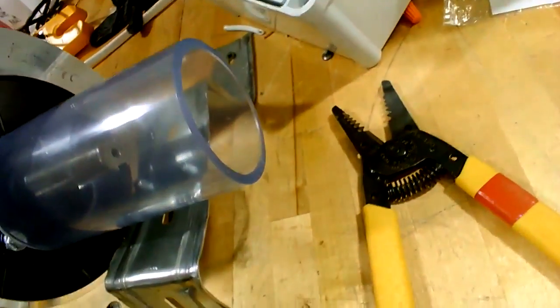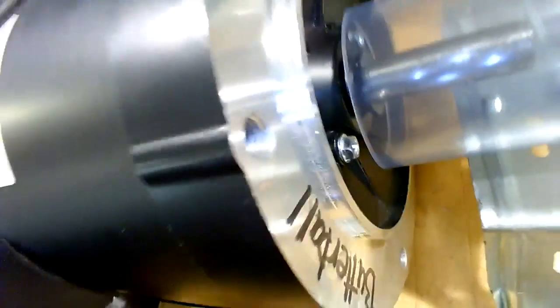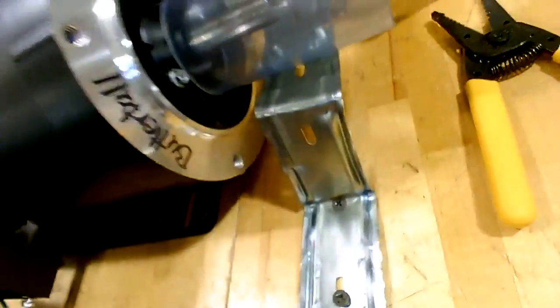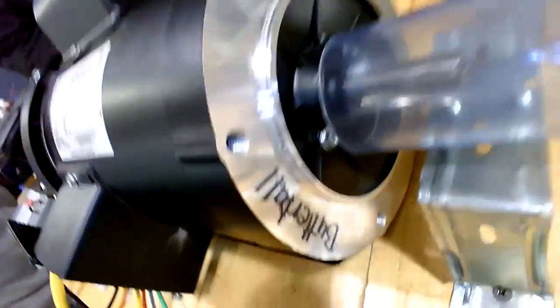It either means that the pump you're driving might have bad bearings in it. It may be in a bind. Your fan may be in a bind. But it's something mechanical that this is driving could be bad. If it's drawing more than the nameplate, or the bearings in the motor could be going bad. When they begin to go bad and they start to drag and squeal, then it's going to be drawing too many amps.